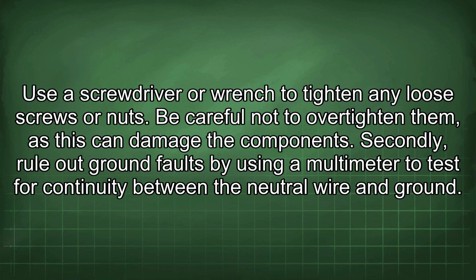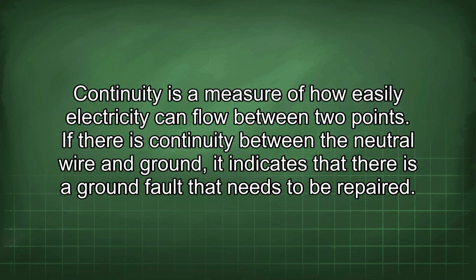Be careful not to over-tighten them, as this can damage the components. Secondly, rule out ground faults by using a multimeter to test for continuity between the neutral wire and ground. Continuity is a measure of how easily electricity can flow between 2 points.